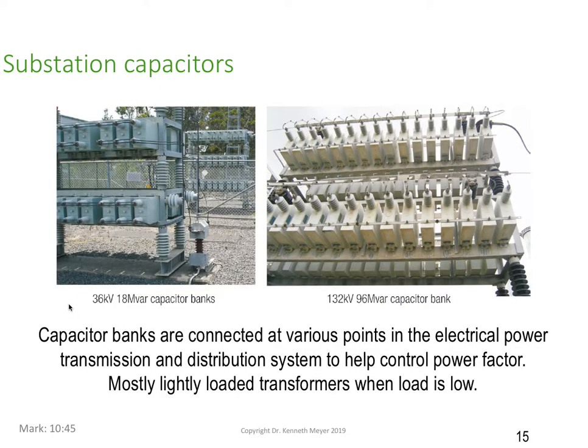Other places you can see capacitors is in high voltage substations. So the supply authority themselves, you'll often see these in the high voltage switch yards. This first drawing here, you can see that's a 36 kV, so 36,000 volts. And it has 18 MVAR, you'll notice that's 18 megavar capacitor bank. So they actually switch the bank in a couple of stages, just depending on what's needed.